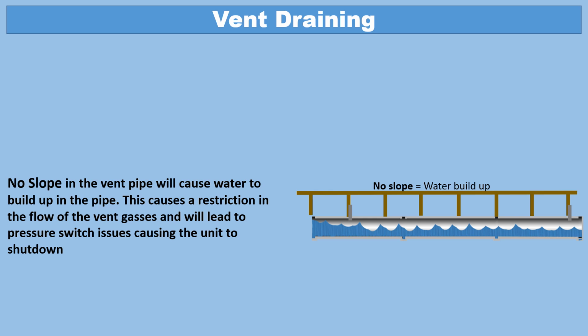No slope in the vent pipe will cause water to build up in the pipe. This causes a restriction in the flow of the vent gases and will lead to pressure switch issues, causing the unit to shut down.